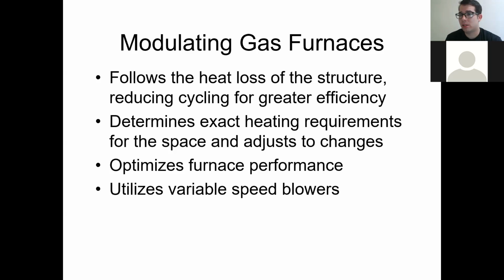The main thing is to look at the full pressure when it's producing 100% heat. Now, like I said before, you can either crank a thermostat way up, or for these ones, on the control board there's still going to be thermostat connections for R, which is your 24-volt power, and W, which is your call for heating. If you take a pair of jumpers and jump R to W, you're going to have the heat kick on at full speed, max heat.